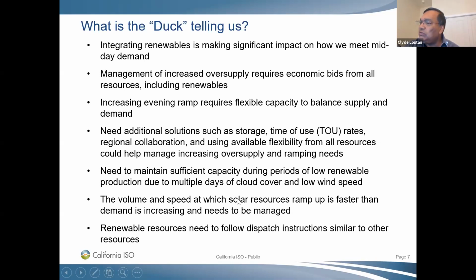What we also notice is during sunrise, the speed at which the solar comes out is very fast. And you do not have the load to consume the solar that's coming up. And not only the grid connected solar, because we have control of the grid connected solar, but as I mentioned, we got over 12,000 megawatts of rooftop solar PV, and you have no controllability on that. You have no visibility. So that creates a huge challenge for system operators in that you got to control a grid through a market every 5 minutes and through automatic generation control every 4 seconds.